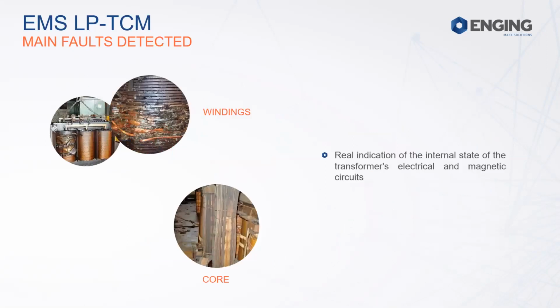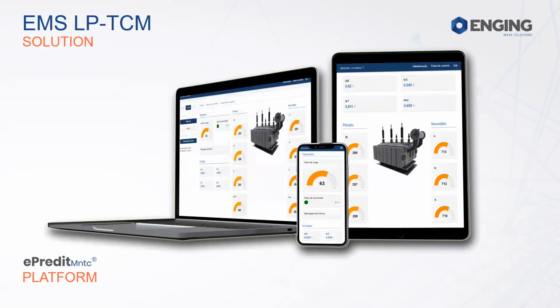So in this case, and a little bit different from the TCM, from the power transformer solution, the low power transformer EMS LPTCM will be able to detect and give you a real indication of the internal state of the transformer. It's like an on-off system that in the end will give you the fault detection on windings and core, but will not at this moment pinpoint where the fault is. It will give you the information: you have a fault or you don't have a fault.